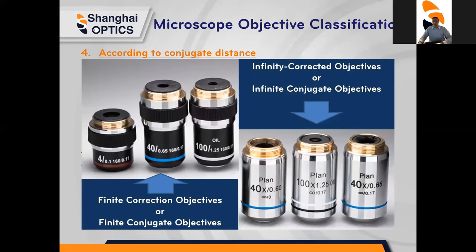According to the conjugate distance, an objective lens may be classified according to conjugate distance. For example, finite correction objectives or finite conjugate objectives will have a limit or specific number, while infinity corrected objectives or infinite conjugate objectives have no limit.